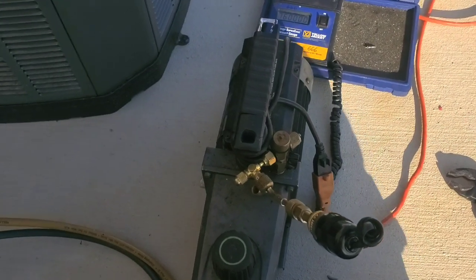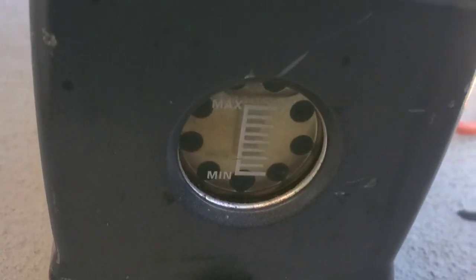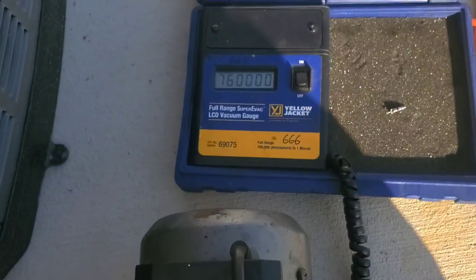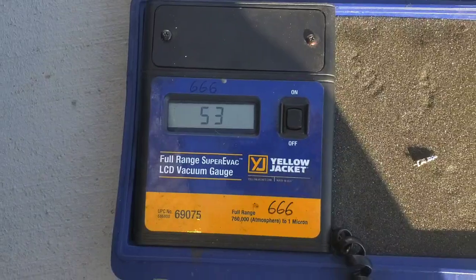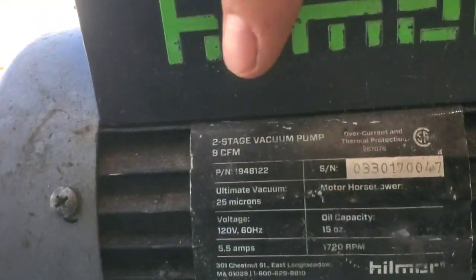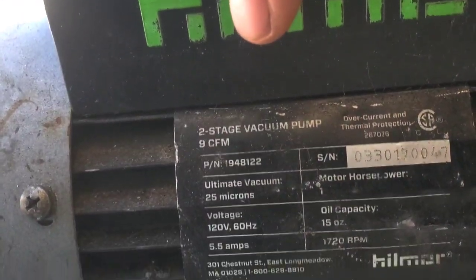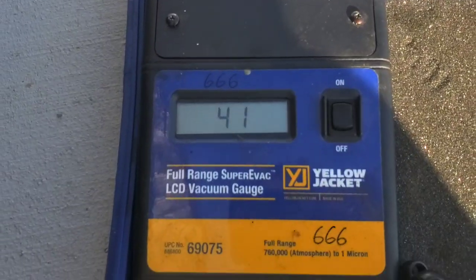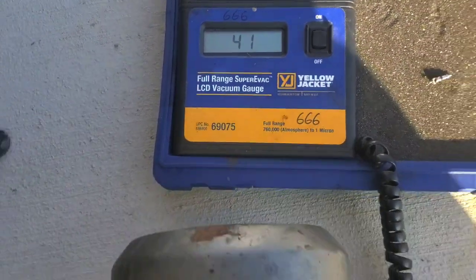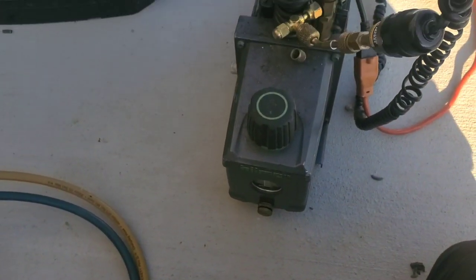This vacuum pump hasn't had its oil changed in years. That's what the oil looks like. I wonder if it can pull a vacuum. That's pretty good. Ultimate vacuum, 25 microns. So I guess it's not doing ultimate vacuum, but it's doing sufficient vacuum.